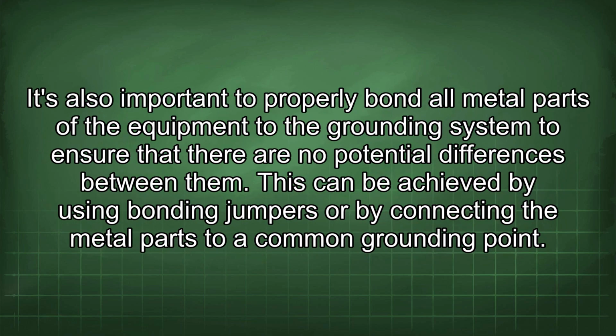It's also important to properly bond all metal parts of the equipment to the grounding system to ensure that there are no potential differences between them. This can be achieved by using bonding jumpers or by connecting the metal parts to a common grounding point.